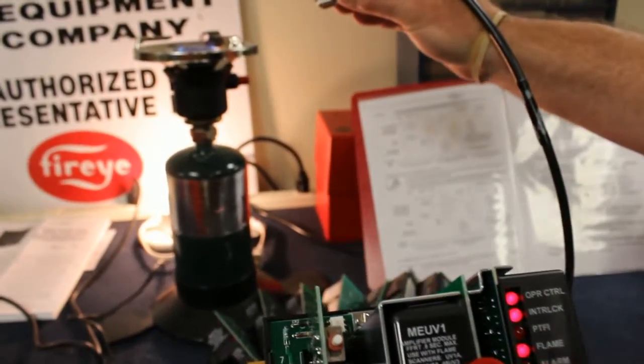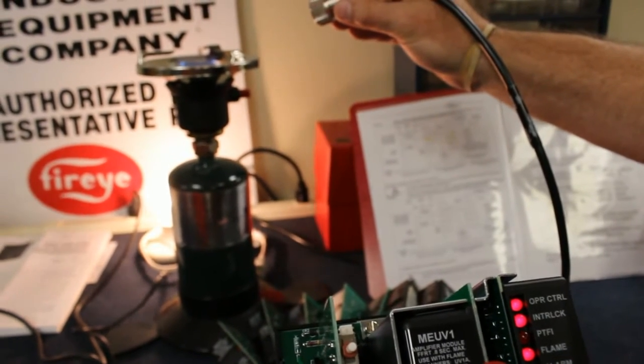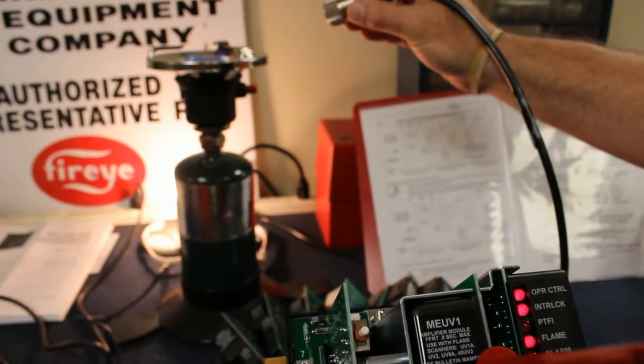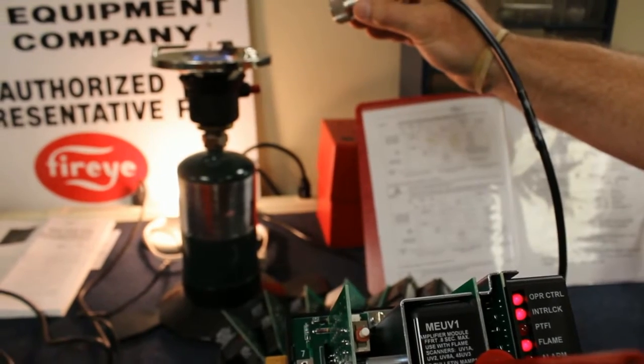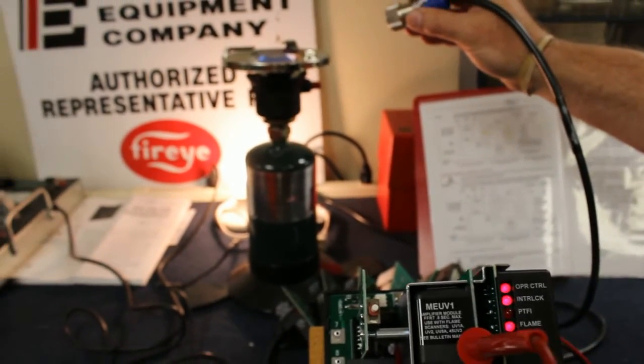That's my ignition transformer. I have 10 seconds to light off to prove flame, and it's in auto. My signal's good.